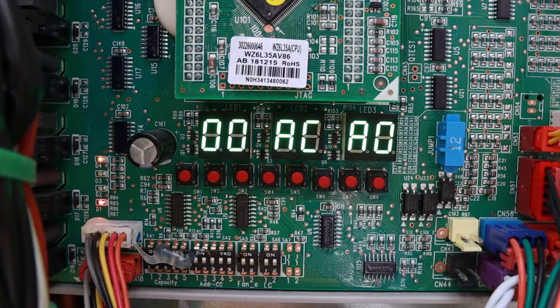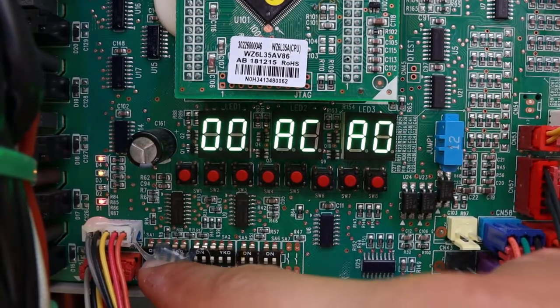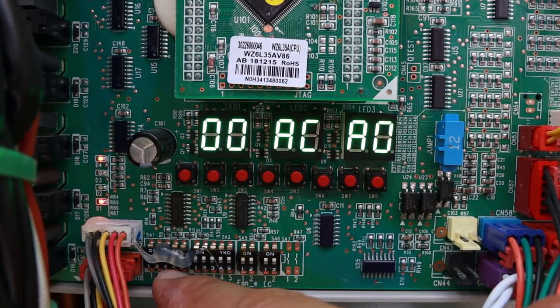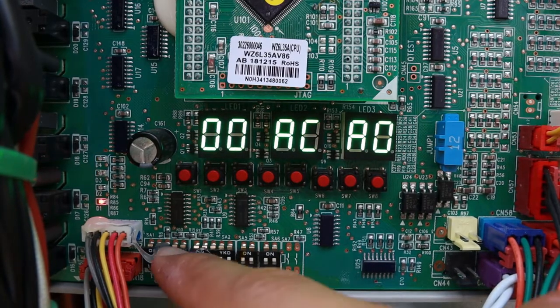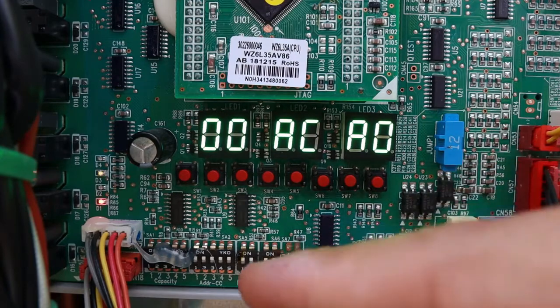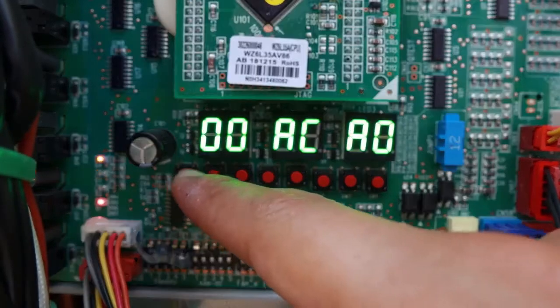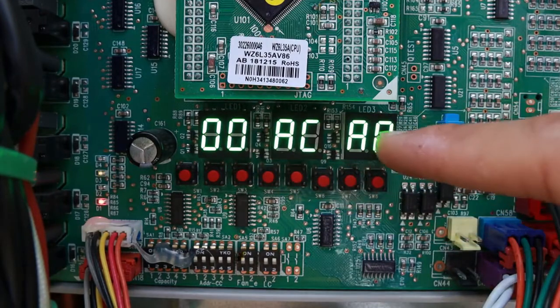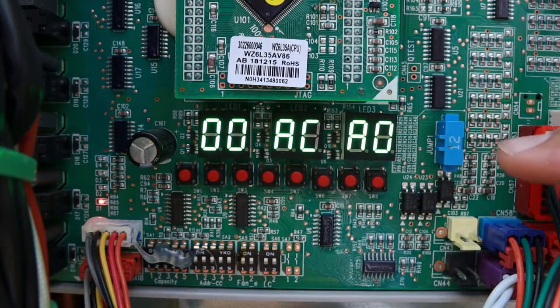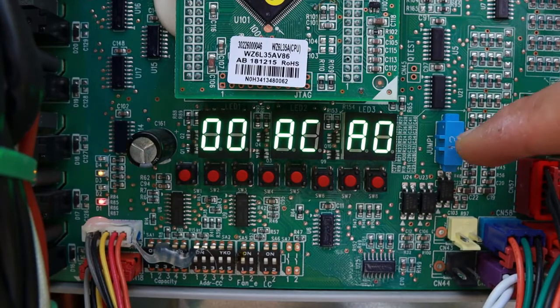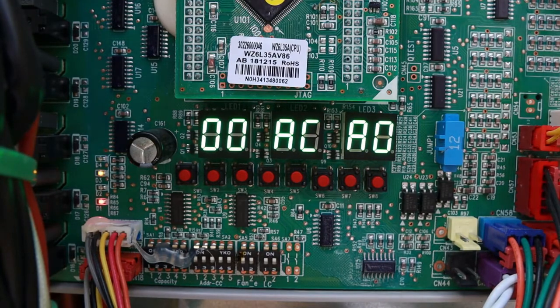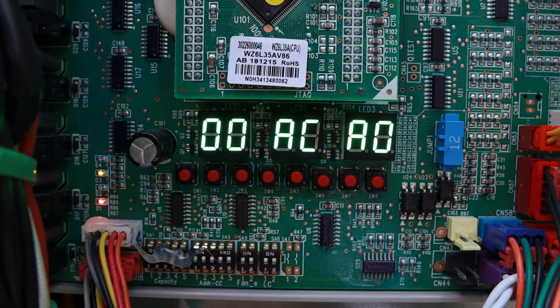Walking you through the board, at the bottom we have the dip switches, including SA1, which is a dip switch for capacity. This one has silicone glue on it — do not touch it or remove it, leave it alone. SW1 through SW8 are the buttons on the main board. We have LED1, LED2, and LED3 showing the display, and a jumper cap right next to it. Make sure this jumper is installed on the board. If it's a brand new unit, you won't be able to miss it, but if you're working on a replacement board, make sure the jumper is there, since a previous technician may have removed it not knowing what to do with it.